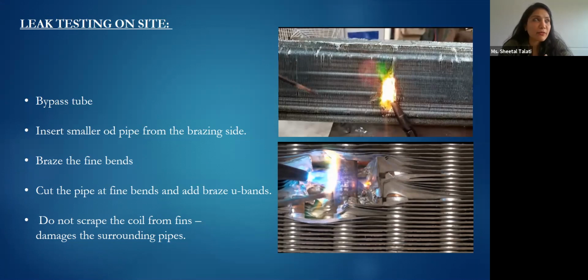We usually get complaints that the coils are leaking from the non-brazing side, that is the fine bend side. In that case, we recommend you cut those fine bends and add U-bends. If not that, you can use a brazing rod and simply braze the fine bends. Do not scrape off the fins, because you use a portable torch on site and the surrounding pipes start leaking everywhere. The damage is already done, and then you bring it to the manufacturer to say that the coil is leaking and we don't know what to do about it. Then there is no option remaining but to go for a new coil.